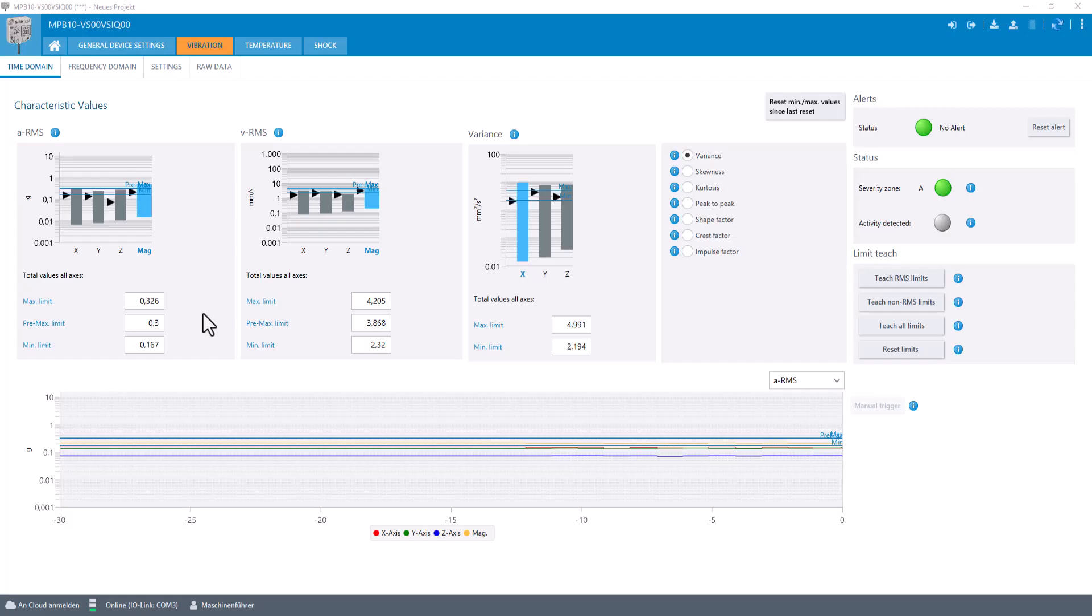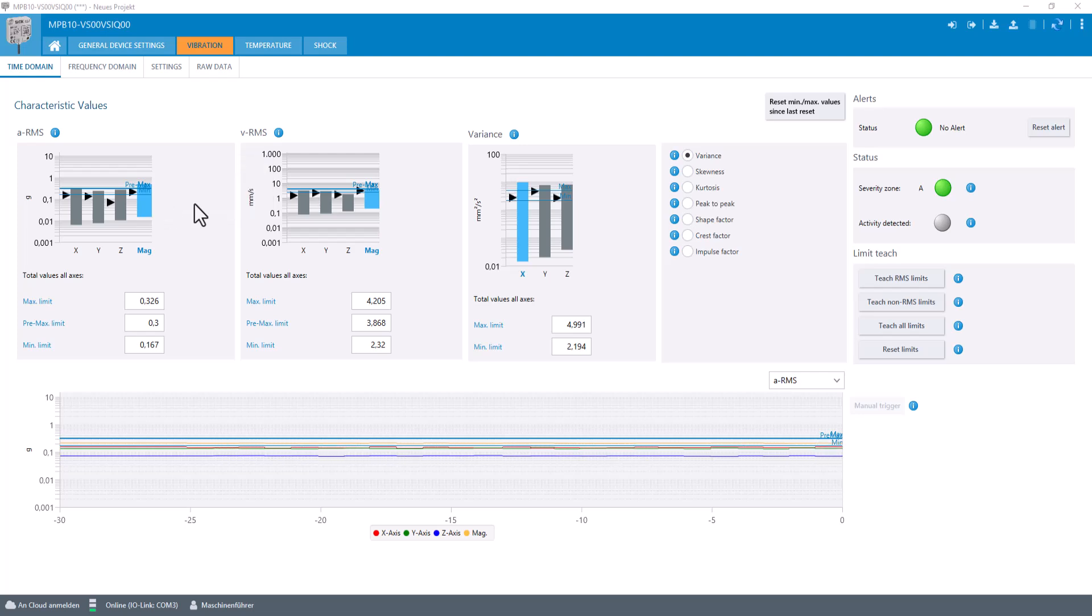Here we see moderate vibration values in time domain. In detail, we observe the strength and the energy contained in the vibration by looking at the magnitude of the ARMS and the VRMS.